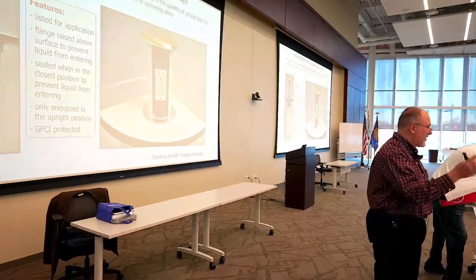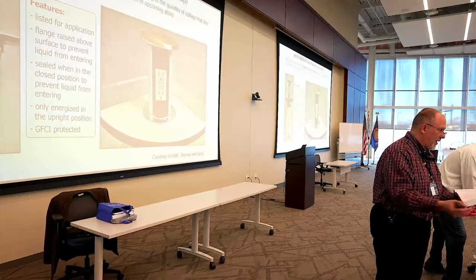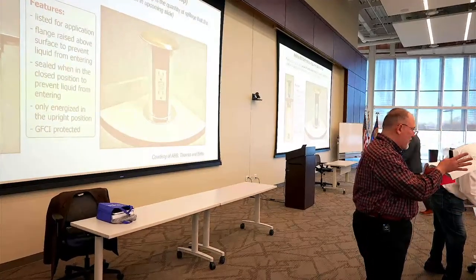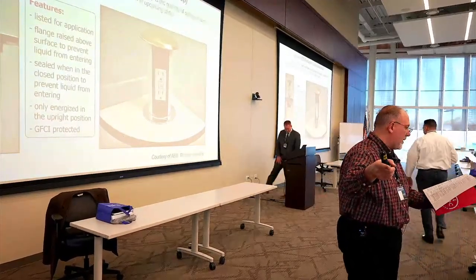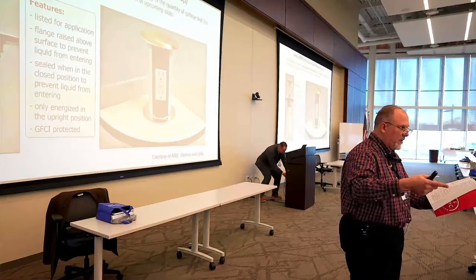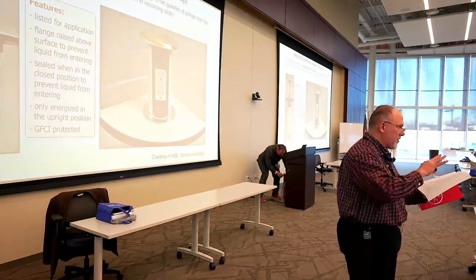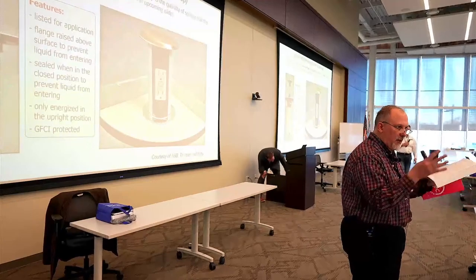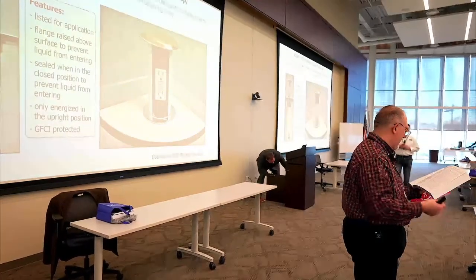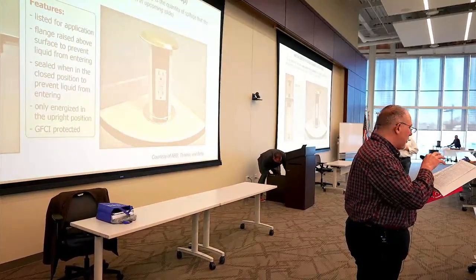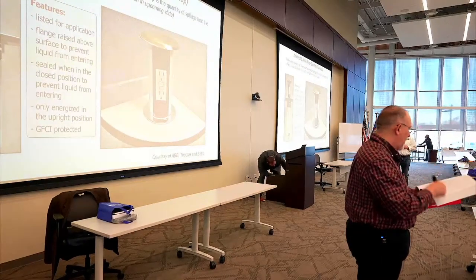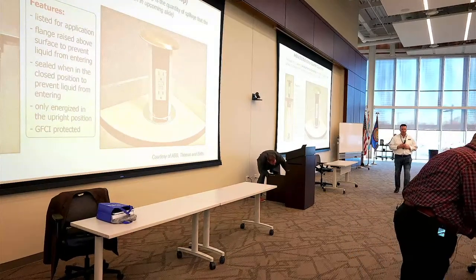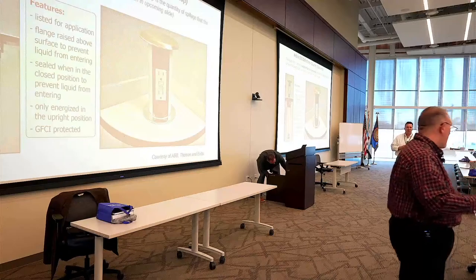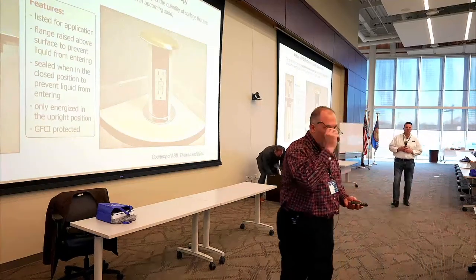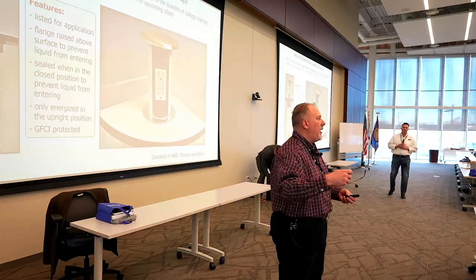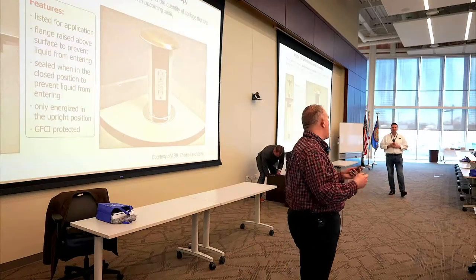This is the magic of the book, right? You just can't sit in one code section. You got to remember 406 is on receptacles, cord connectors, attachment plugs, panel boards, transformers, all that good stuff, but you still got to follow the rules in Chapters 1 through 4, which apply generally. So 406 gives you the receptacle mounting requirements. In the 2020 code is when we added that, and in the 2023 code is when we tried to add clarity on what we mean by receptacles for countertops and receptacles for work surfaces.